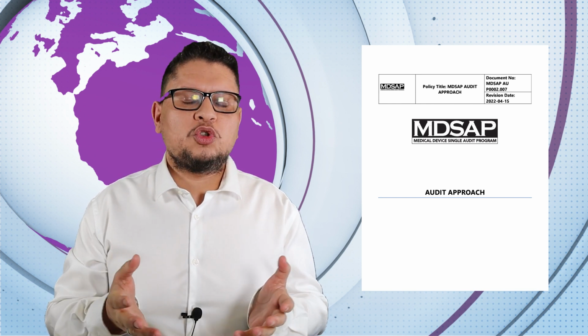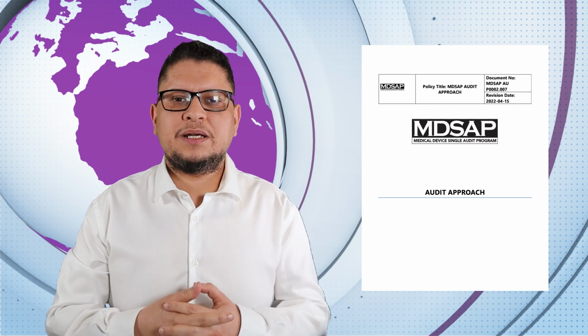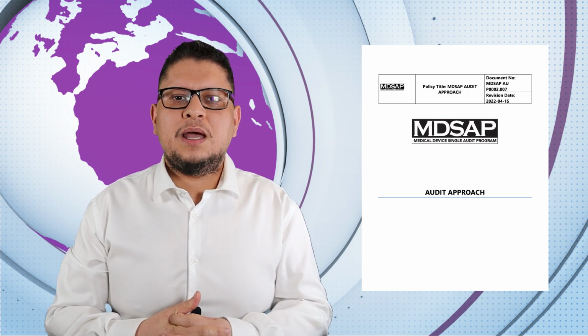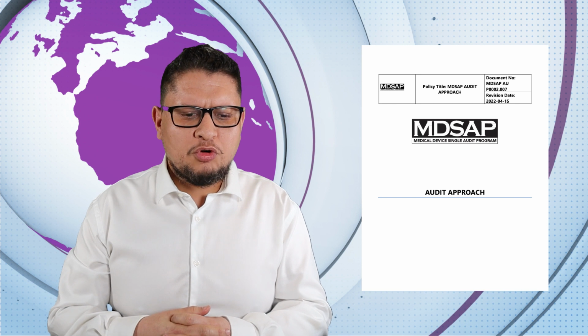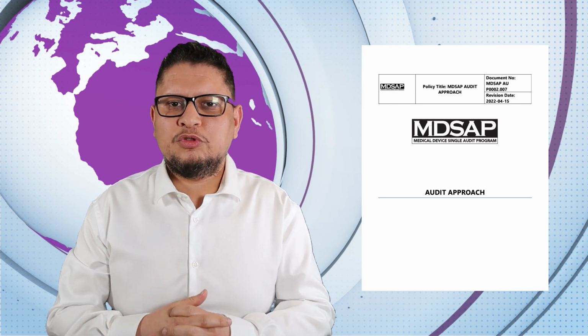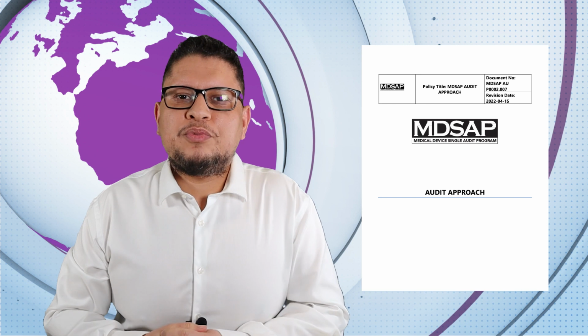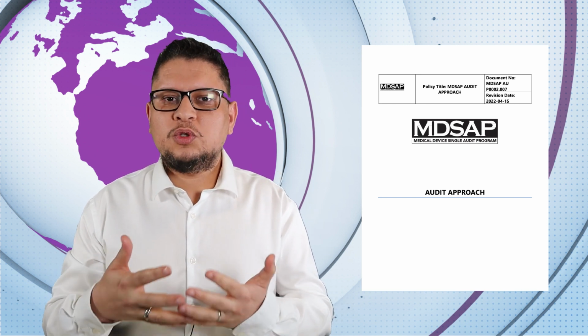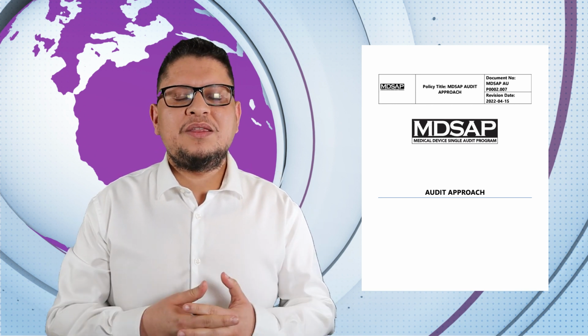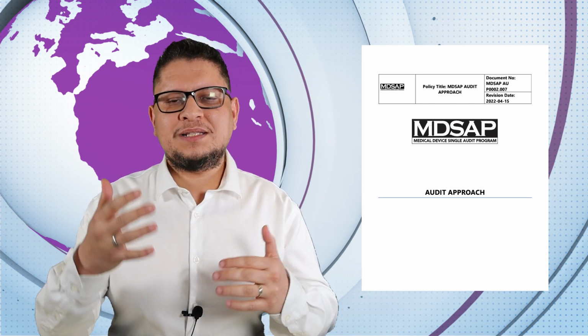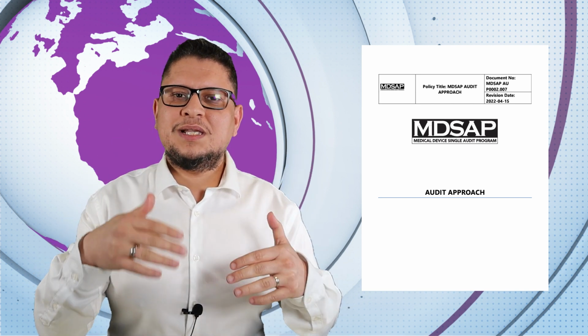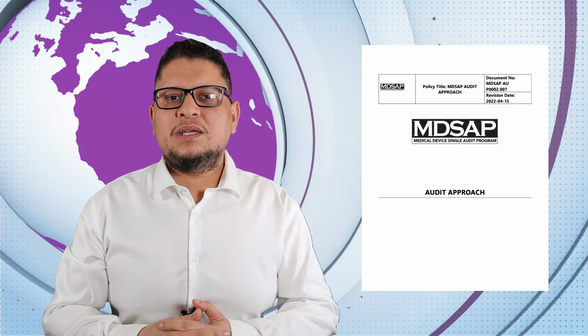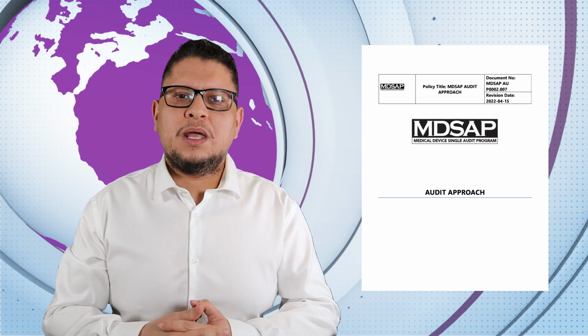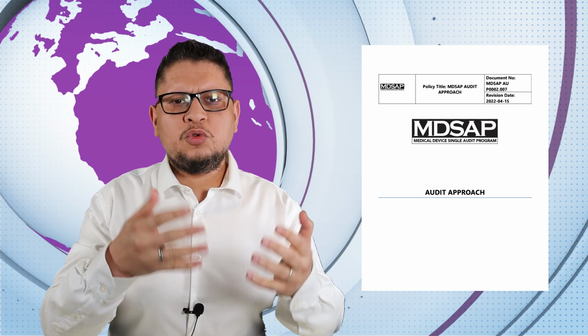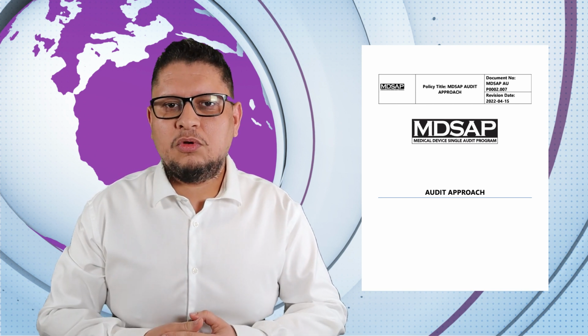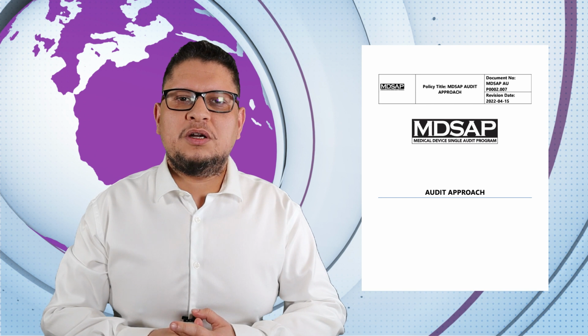And we have a document that helps us understand what will be asked during the audits. It's called the Audit Approach. So this Audit Approach was updated. If you were using it, you have to update that. There is a full list of the updates at the end of the document. It tells you exactly what has changed. So if you are using it for preparing your MDSAP audit, then you can go there and update this document per the new requirements.